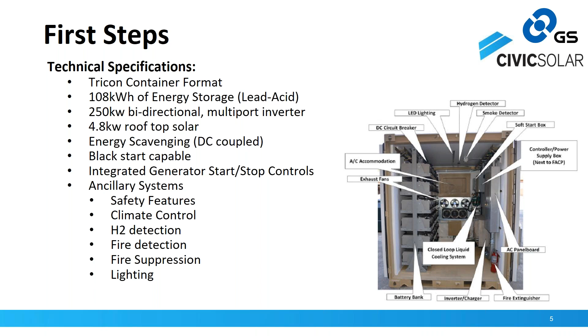So we developed a number of other rescue type units. We did one that was 120 kW and 240 kilowatt hours in a 20-foot shipping container. Then for larger applications, we started to separate our energy modules from our power modules, with a 20-foot container full of nothing but batteries, 528 kilowatt hours, and another that was nothing but power modules, with 90 kW of power available.